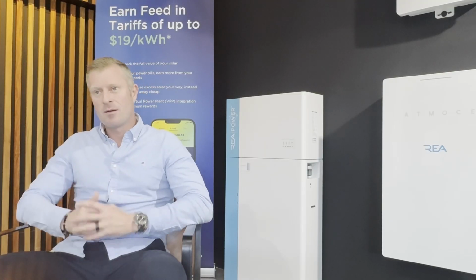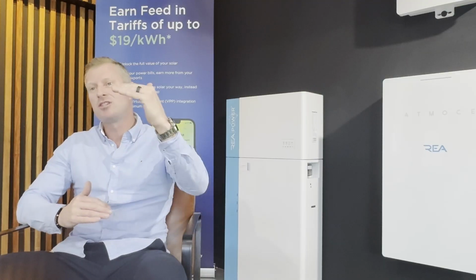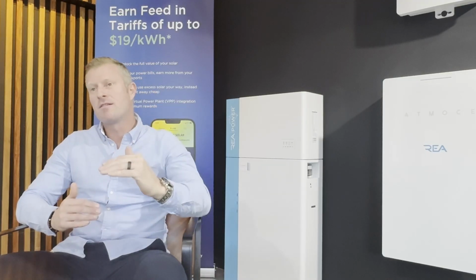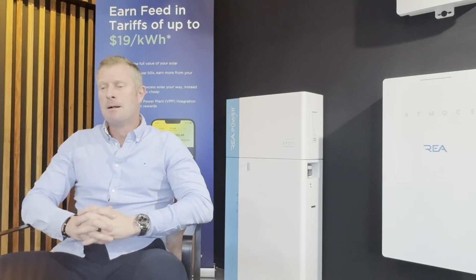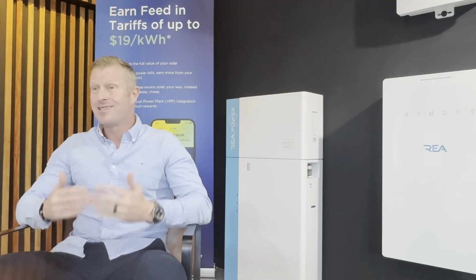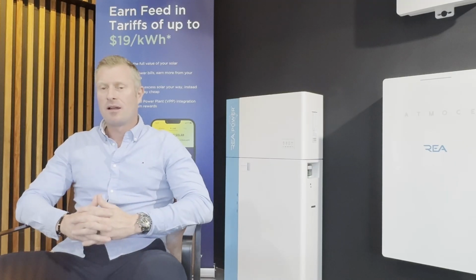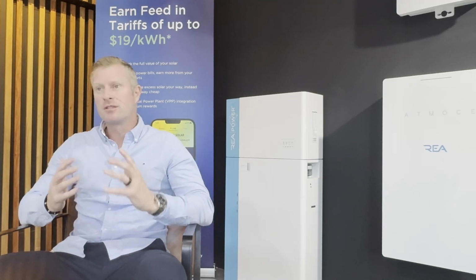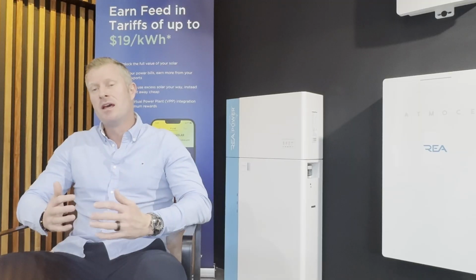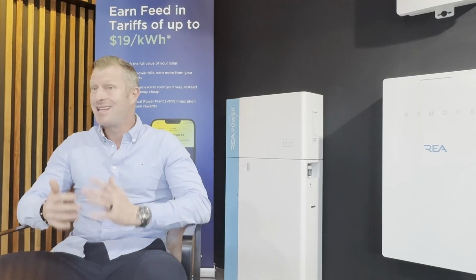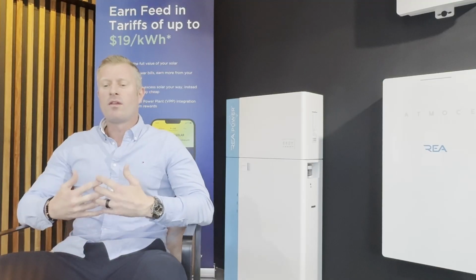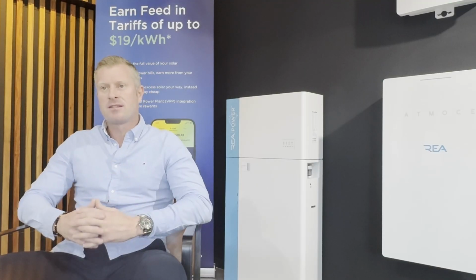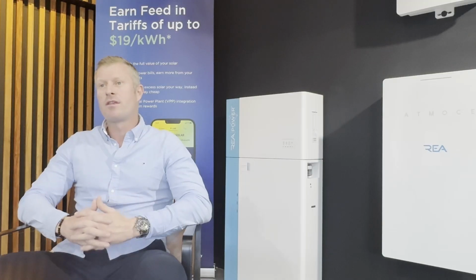Essentially when you're converting the energy, you have multiple stages and what's called a DC boost to boost the energy up above 400 volts, then reconvert it down to 240 volts AC. The problem with direct current, and what REA have always advocated for, is safe and circuit-protected solar. Unfortunately with high voltage systems and batteries, that's why they have built-in fire extinguishers and fire mitigation - because there's a potential for a high voltage DC arc fault. We're firm believers that safety is the most important thing when looking at a battery.